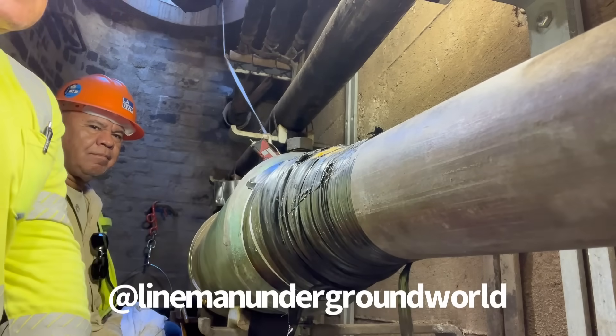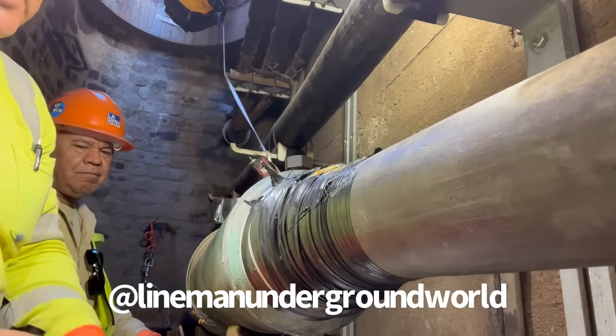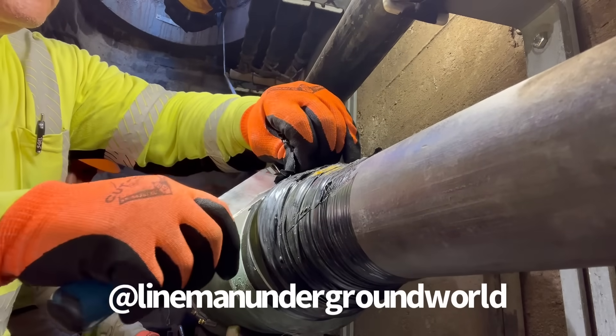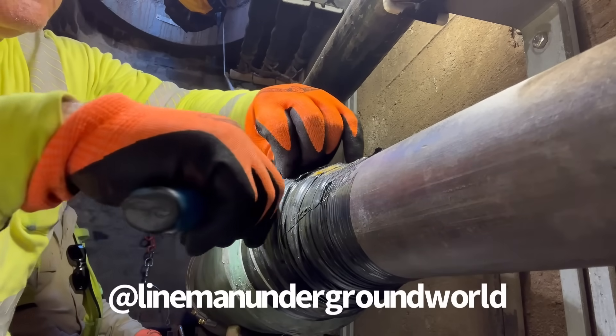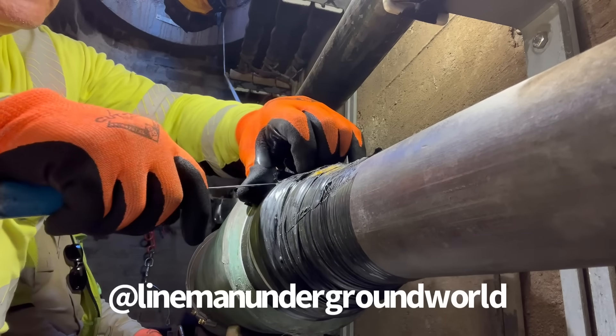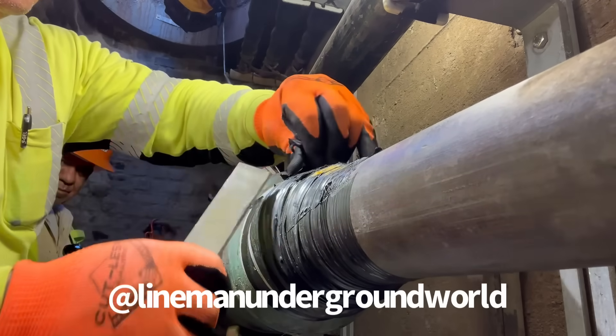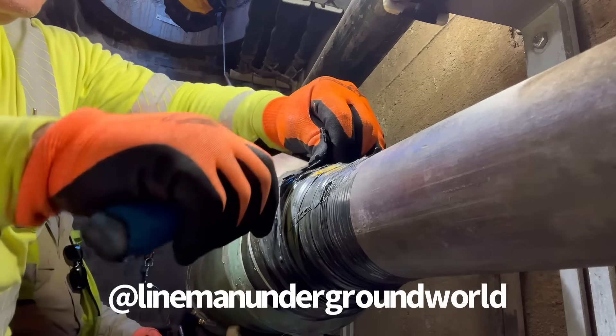What we decided to do is just take the three-quarter off and re-tape it because of that other sealant they put there. It might be worse than I think, so we don't want to disturb it too much, but at least we'll stop the leak at the station and get this done ASAP. Because this junction is seeping big time. As long as we can slow down the leak, then we've got it made to get it out.